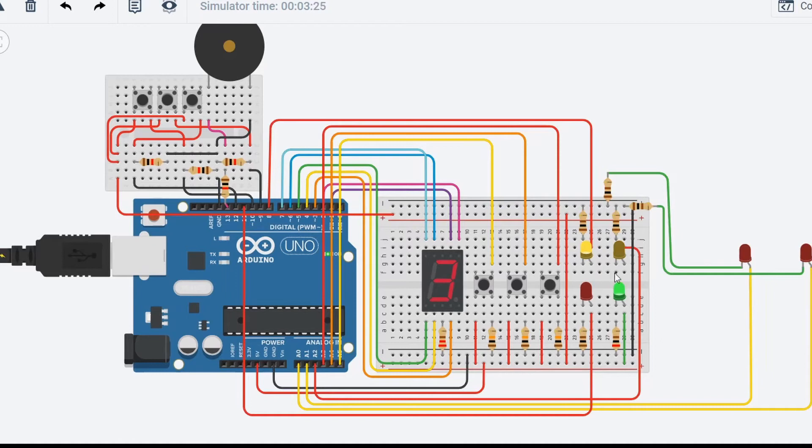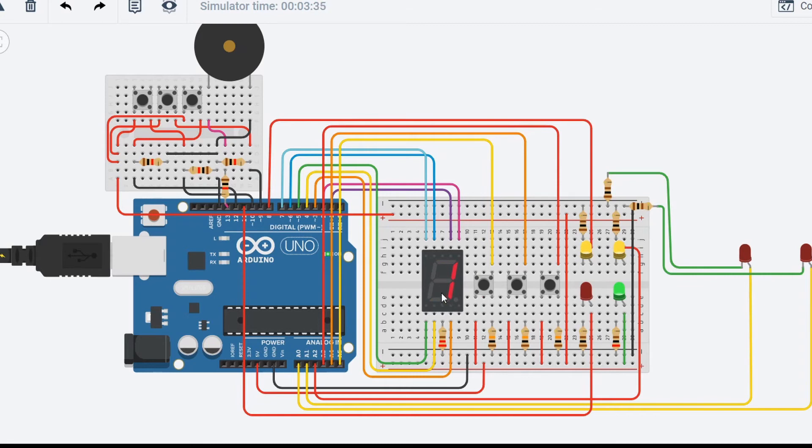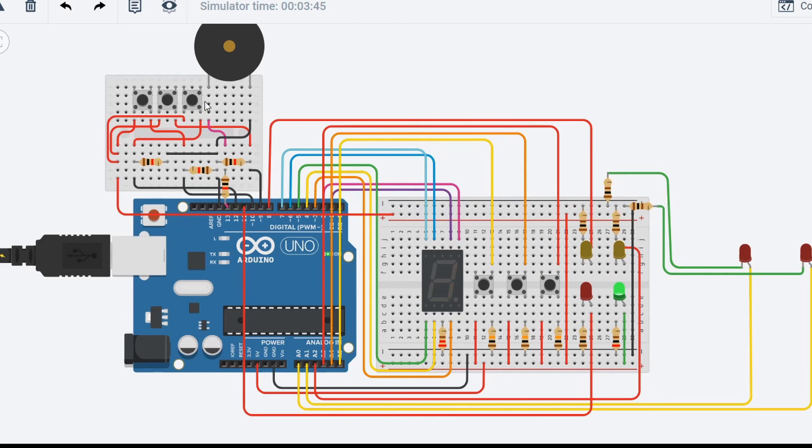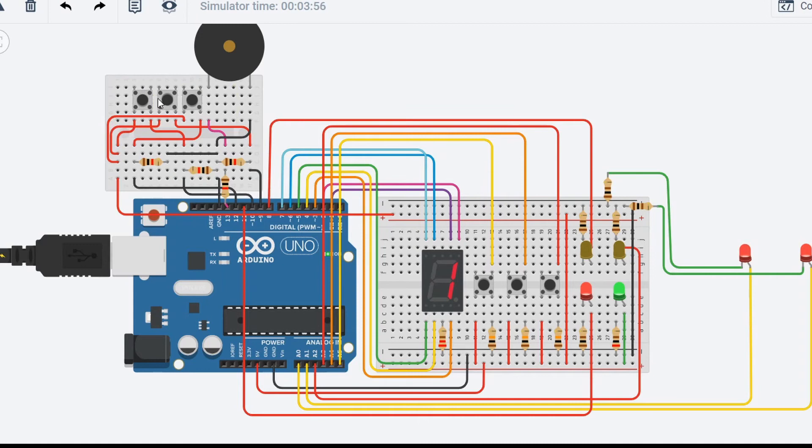So right now I have the horn coding set to march time and the strobe coding just to no sync protocol. So this is going to be on solid, and this is going to be doing march time. I might look a bit slower because the simulation doesn't run at exactly real time because it's kind of hard. So if I do zone one, I'm going to hold that down. I forgot to mention, it has a built-in false alarm prevention. The station has to be activated for two seconds in order for the alarm to be detected. So if it's just clicked once, nothing would happen.